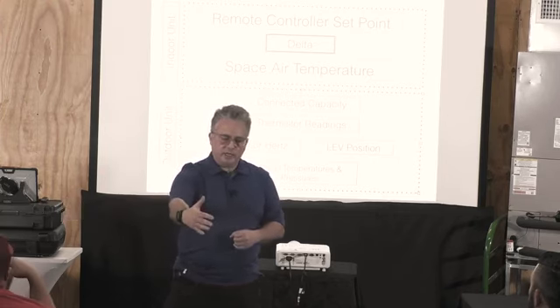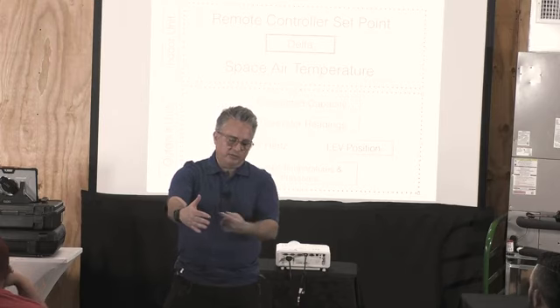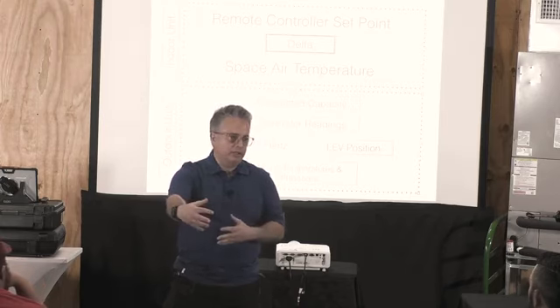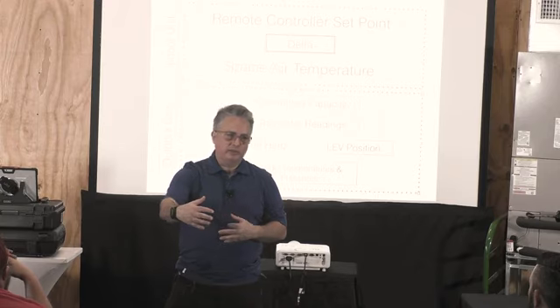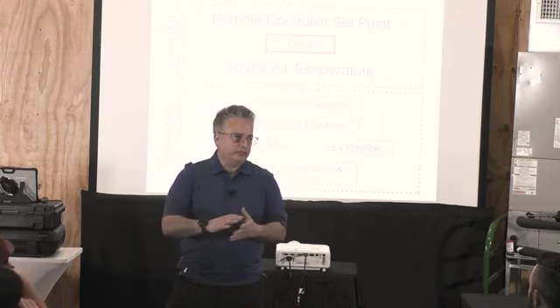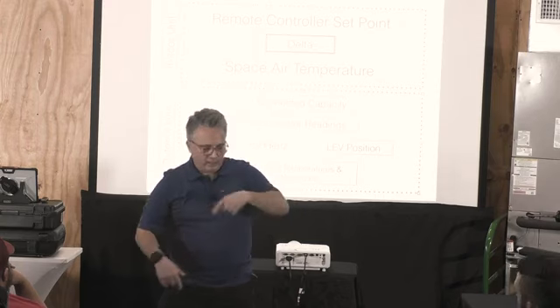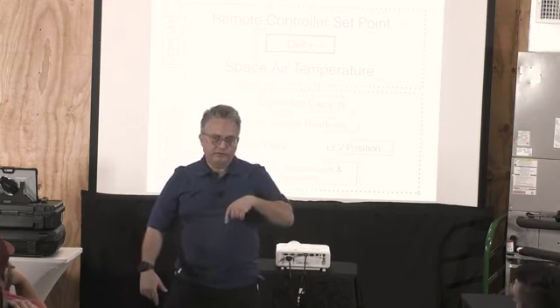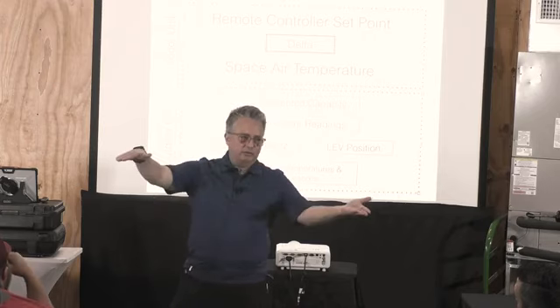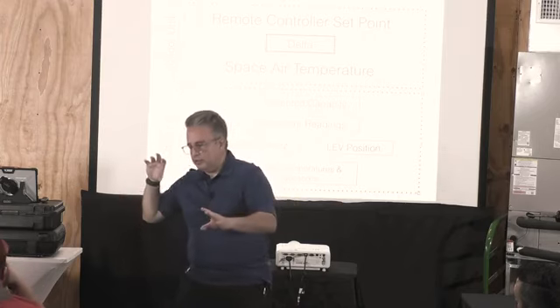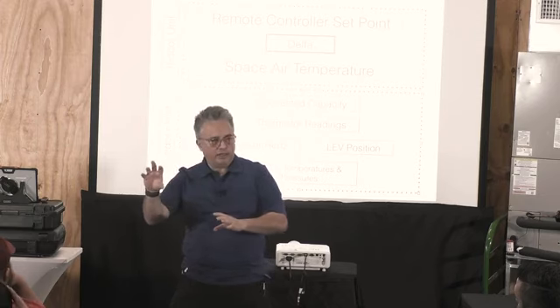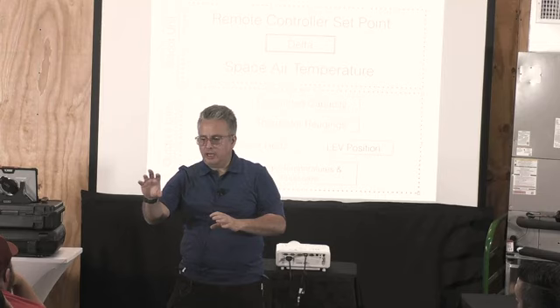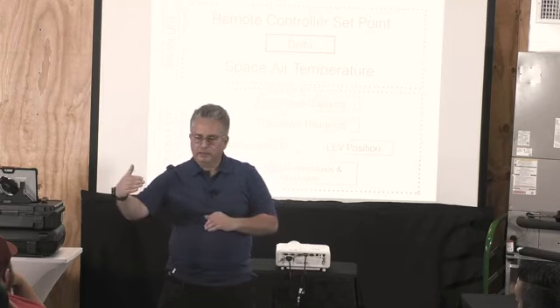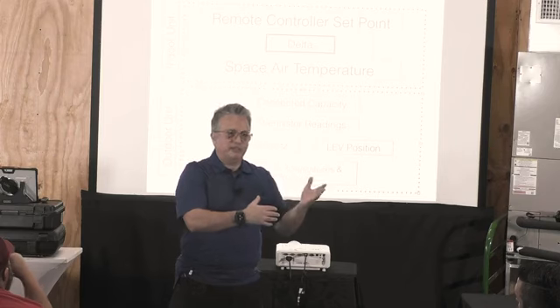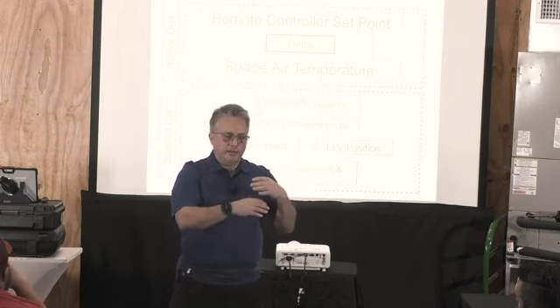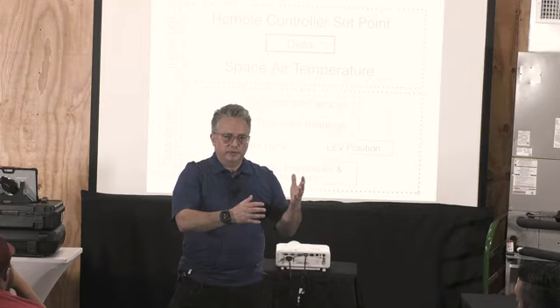Now, at this connection, we don't know where the pipe sensors are, but that part of the coil is going to behave and react differently than the rest of the coil, so it isn't evenly distributed, because in a cassette the coil wraps around. If you have a ducted unit with a return air duct, you can install the ventilation air in the duct, and it may just be on one side of the coil. But what if that side of the coil is in part load conditions? So you see where I'm getting.